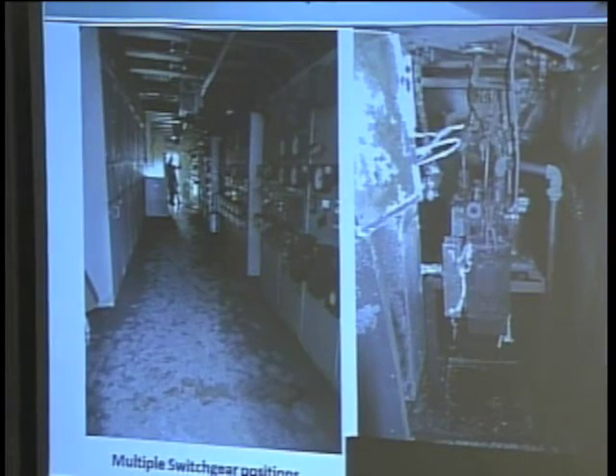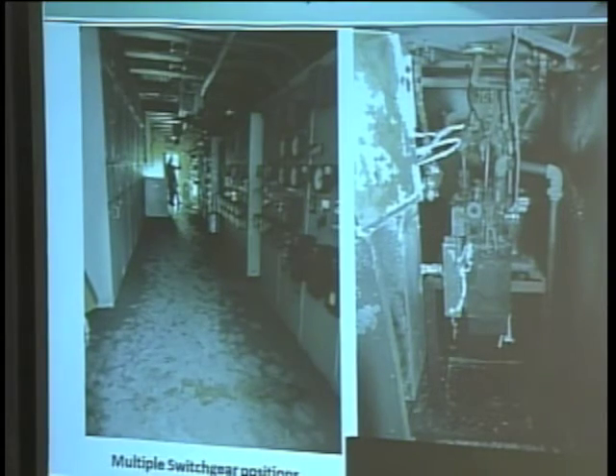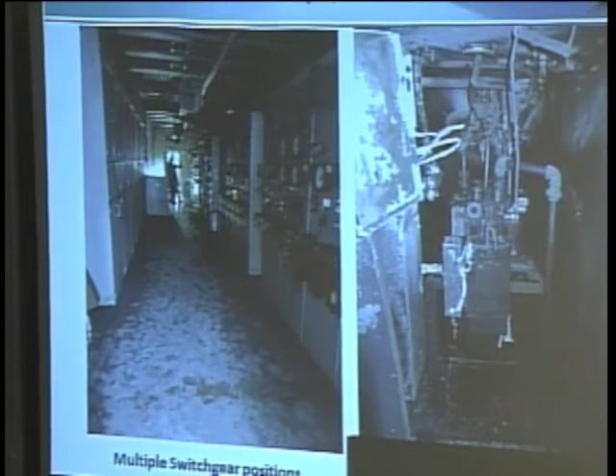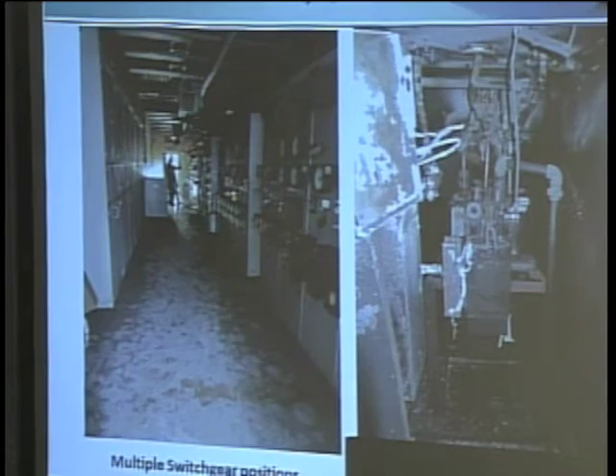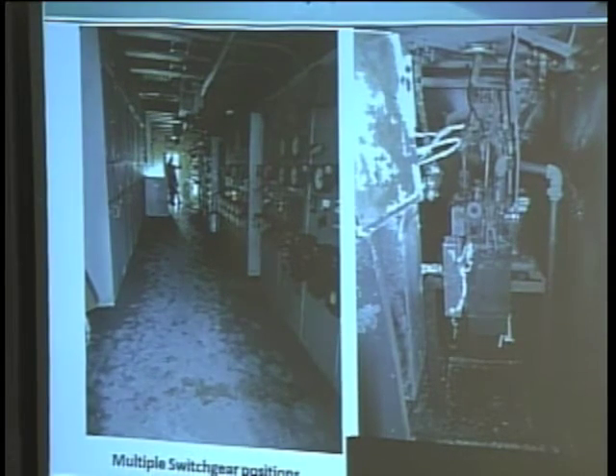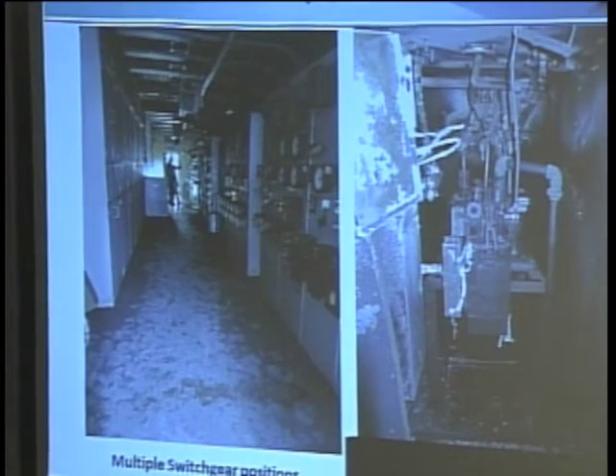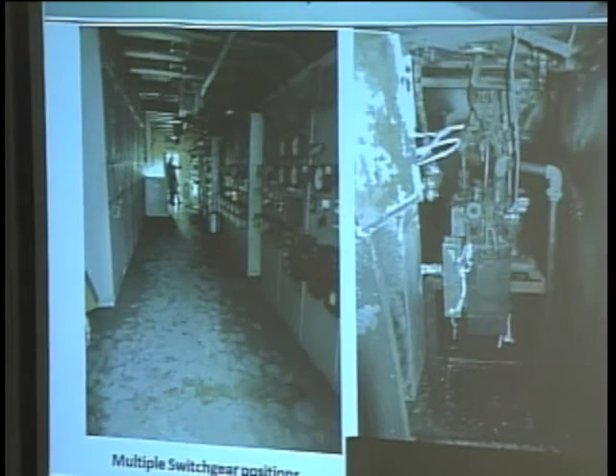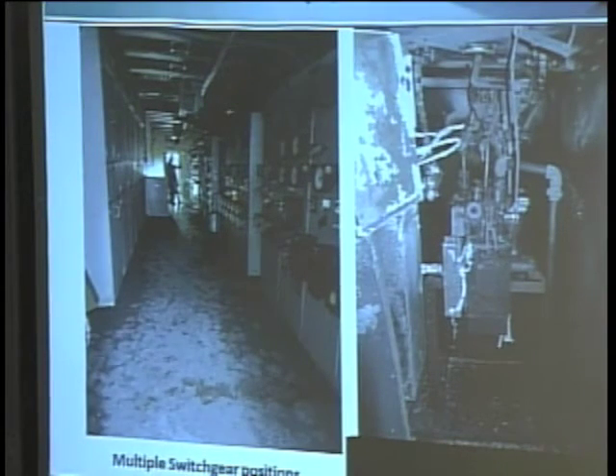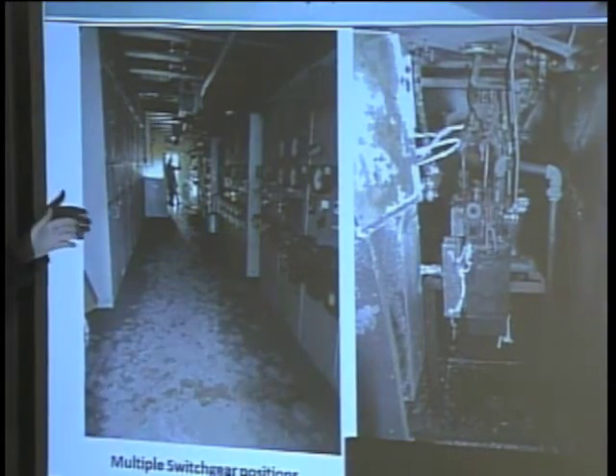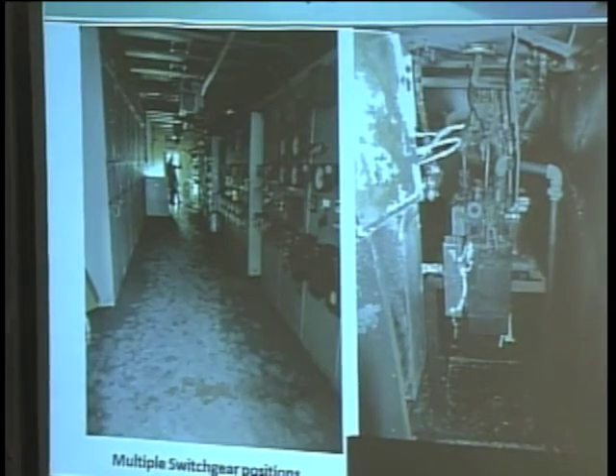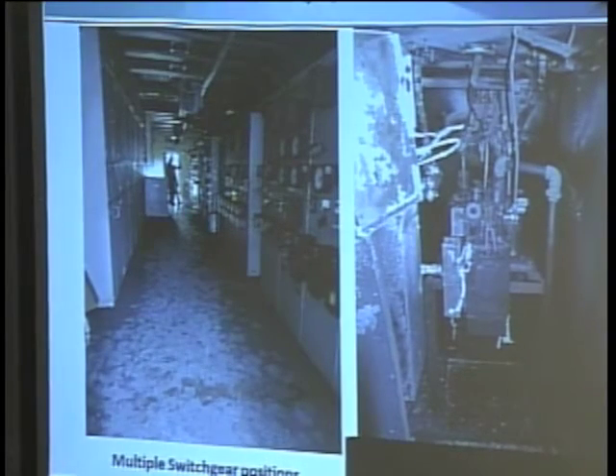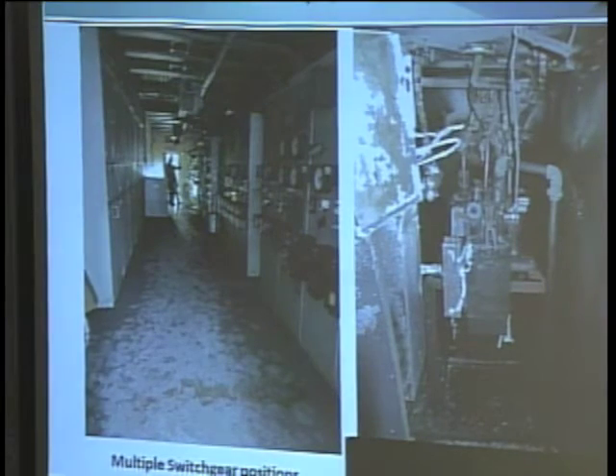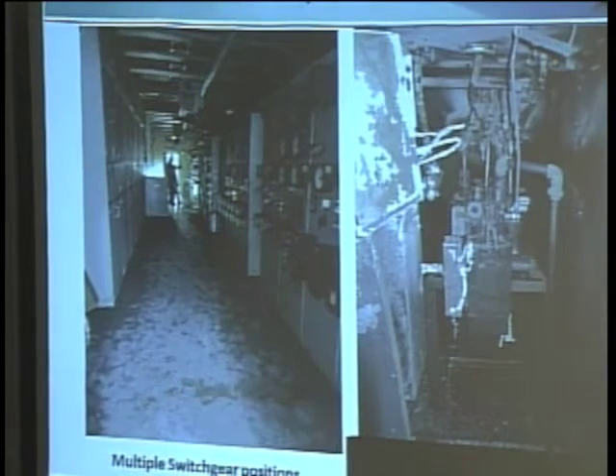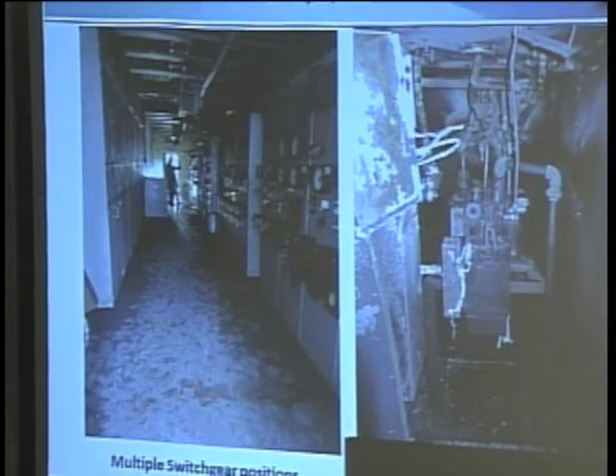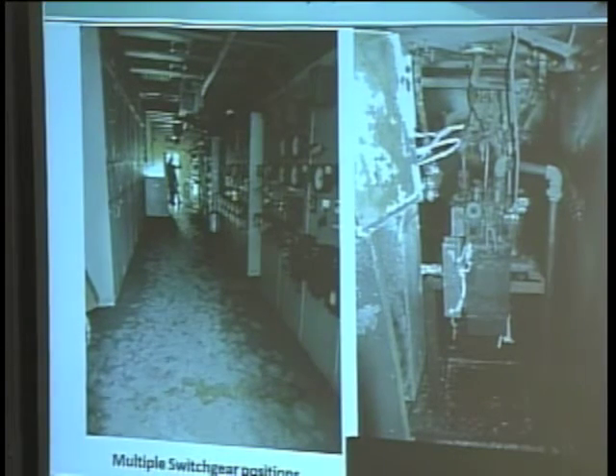So I thought this was an example, and in that position where it is, they had to take two positions out of service temporarily just because it burned up all the equipment and there's no way you could reestablish that. But the other ones, effectively, there was a large fire there, but all this equipment is still undamaged and it just needed to be cleaned up. And that's the process that took them a couple of weeks in order to get it all cleaned up and back to normal.